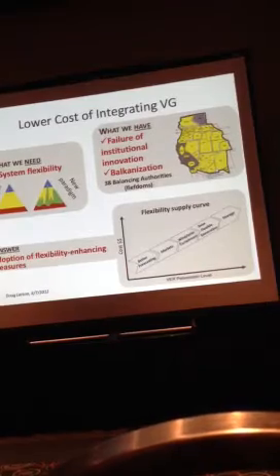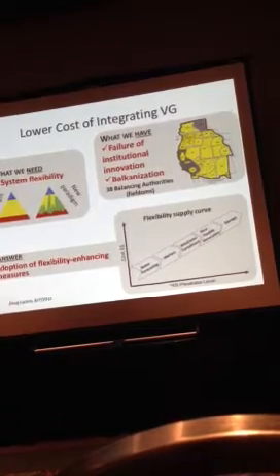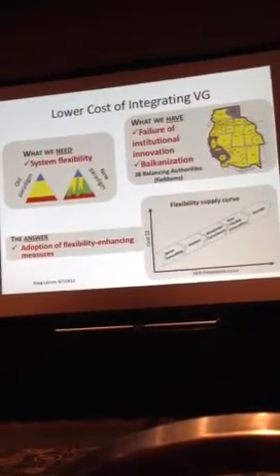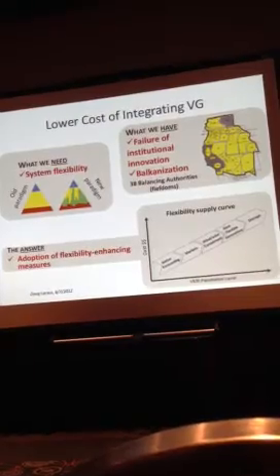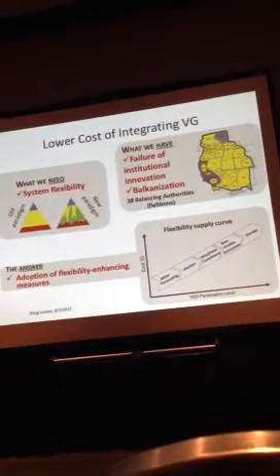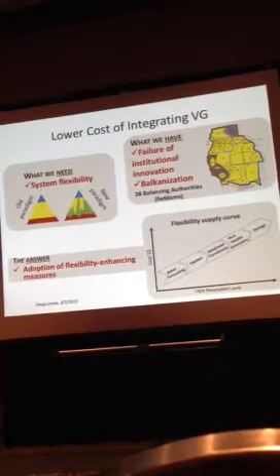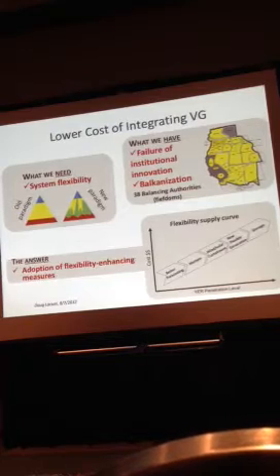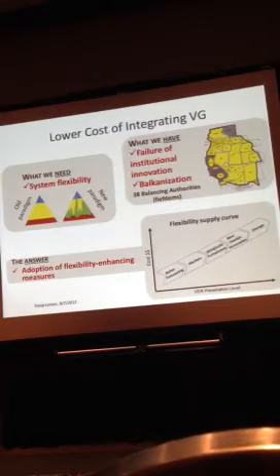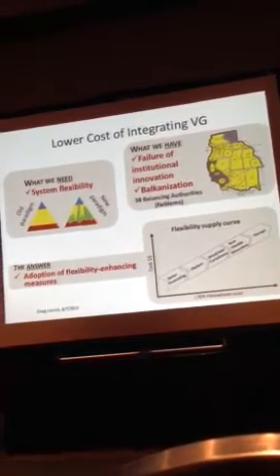This balkanized grid approach to operating the system is becoming increasingly costly as we add more wind and solar, because the variability of load plus the variability of wind plus the variability of solar, when you take that into account in a small geographic area, which is what's largely represented in those 38 balancing authorities, it's really hard to do. Each balancing authority is facing a curve that looks like this. They're meeting that variability by dispatching the generation typically just within their little area. The net result is higher costs to consumers because the system operators have to maintain a lot of generation on standby to meet that variability.